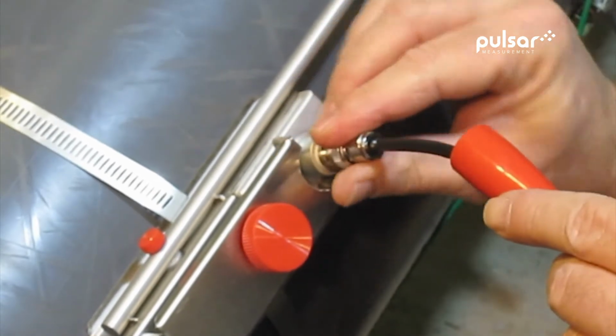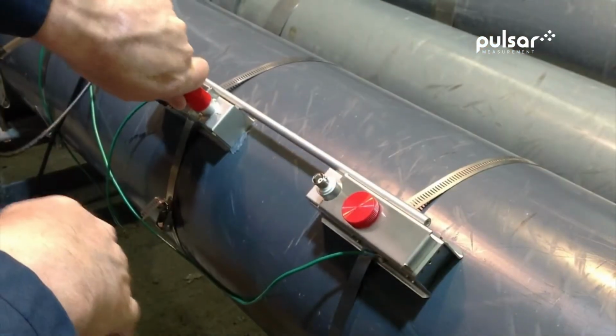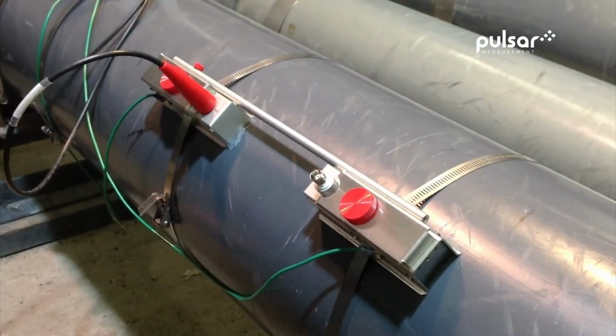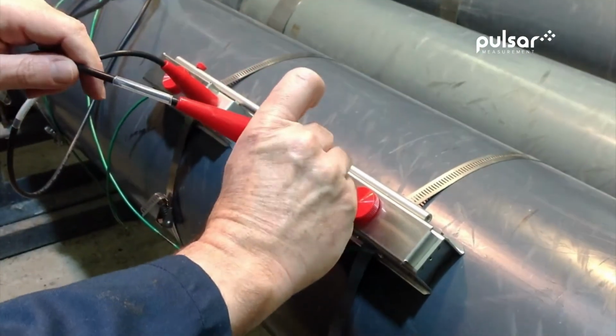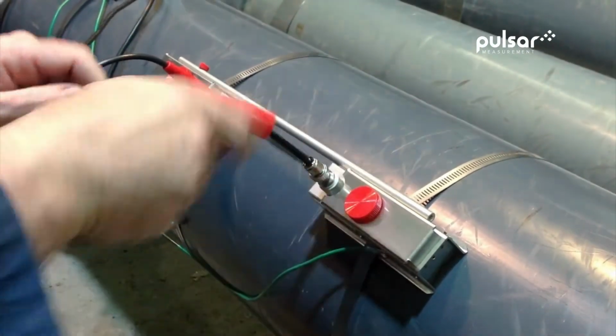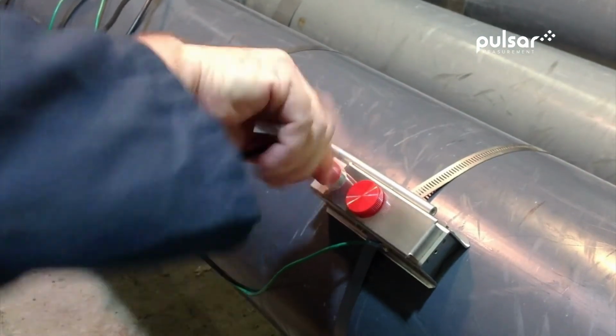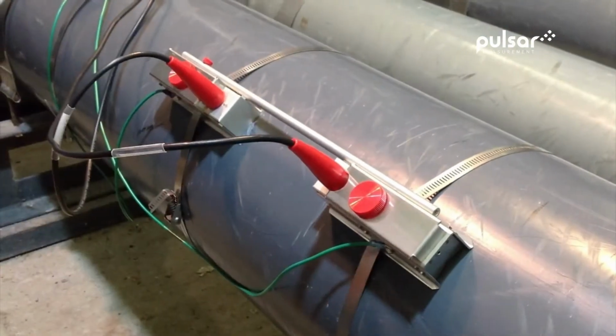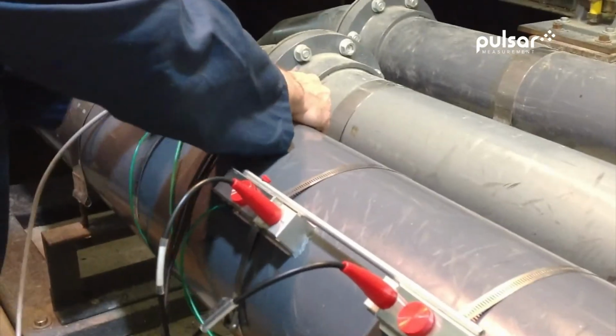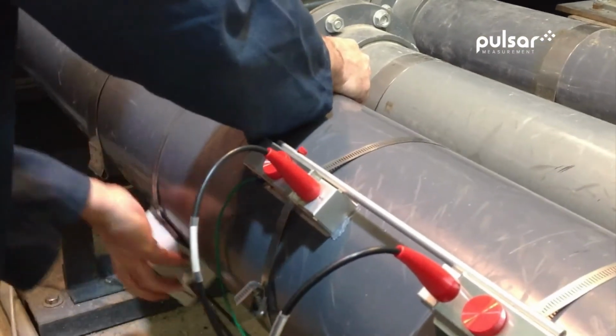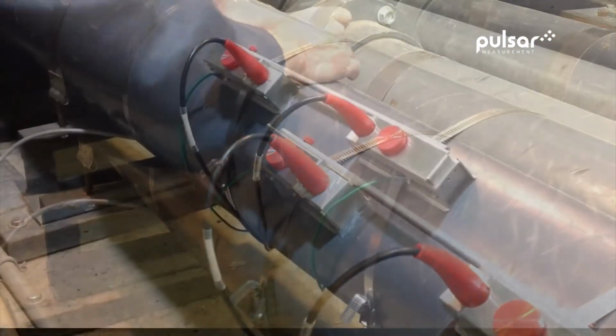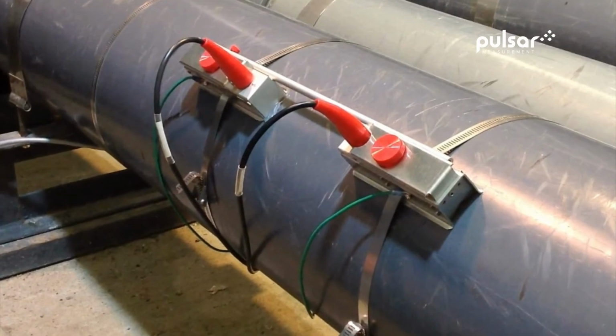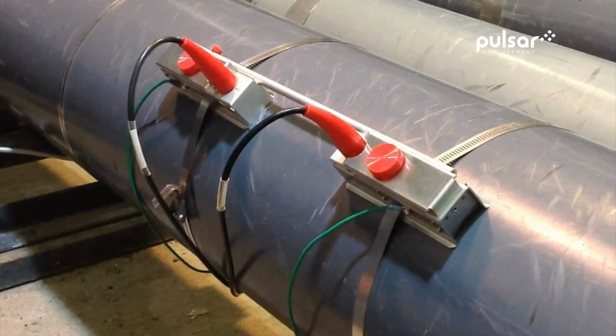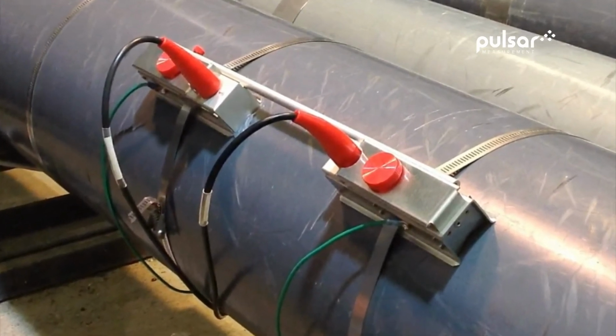The coaxial cables use BNC connectors and couple to the transducer. The BNC connections are protected by seal jackets. These can be filled with coupling compound in wet applications. Here is the completed transducer assembly installed on the pipe, the TTFM 1.0 Transit Time Flowmeter.